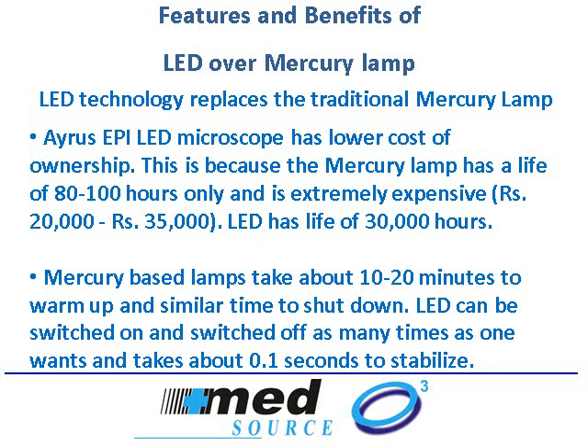Another advantage is convenience. Typically, mercury lamps have a life of about 100 hours and they take almost 20 minutes to start up. That means once you switch on the mercury lamp, you wait for about 10 minutes so that the lamp reaches its peak intensity. Then when you want to switch it off, again the lamp takes about 20 minutes to cool down because it's a very hot source of light. On the other hand, the LED based microscopes like Ayrus EPI, you can just switch on, switch off like a normal lamp. It doesn't take more than 0.1 of a second. So it's quite convenient.